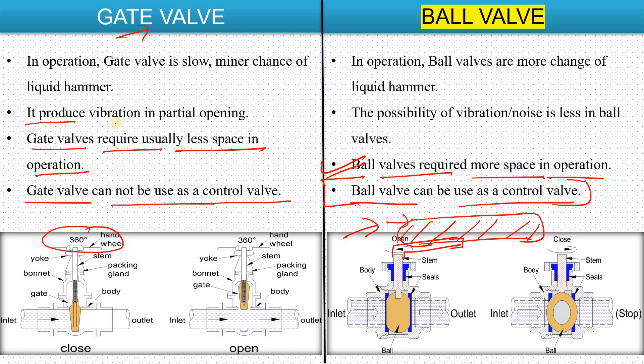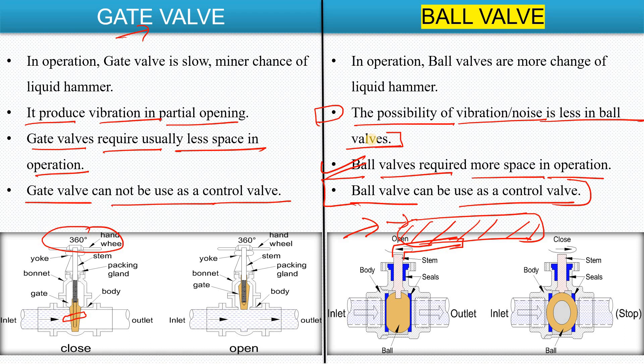Gate valves produce vibration in partial opening — if partially open, vibration and chattering can occur. In the case of the ball valve, the possibility of vibration and noise is less than the gate valve because the disk is a hollow ball, so even if partially open, vibration is comparatively less.